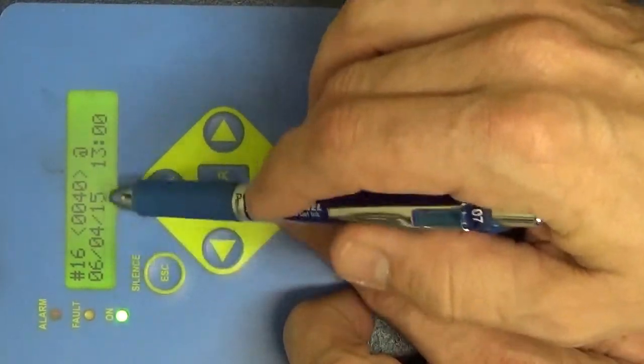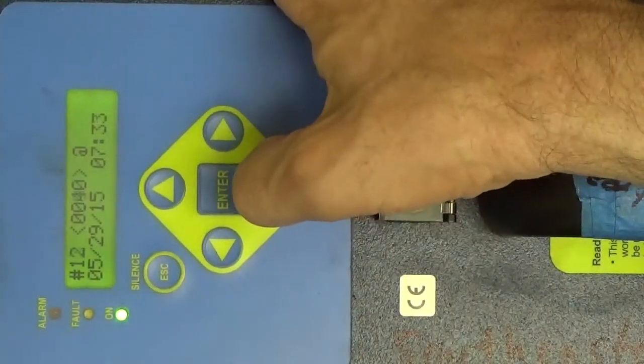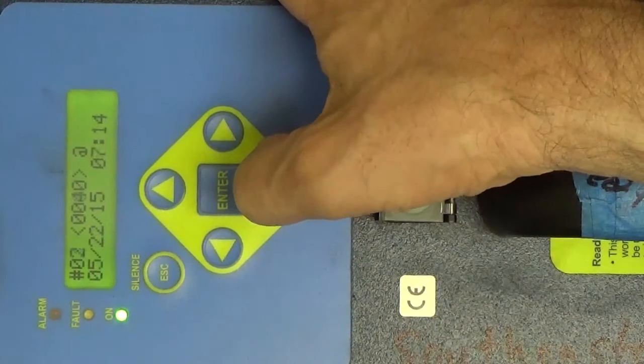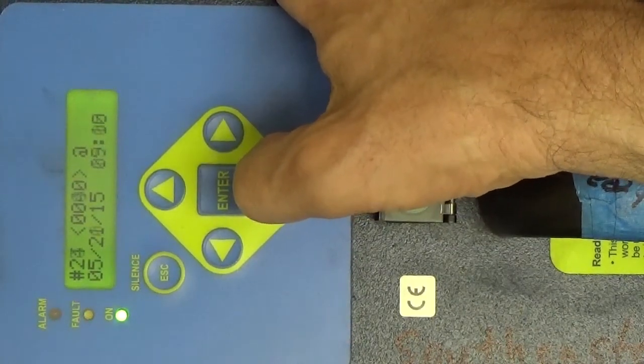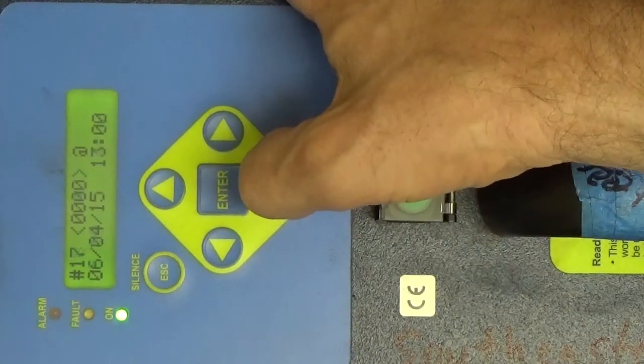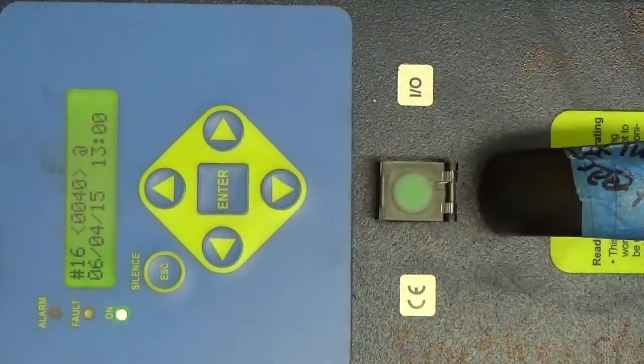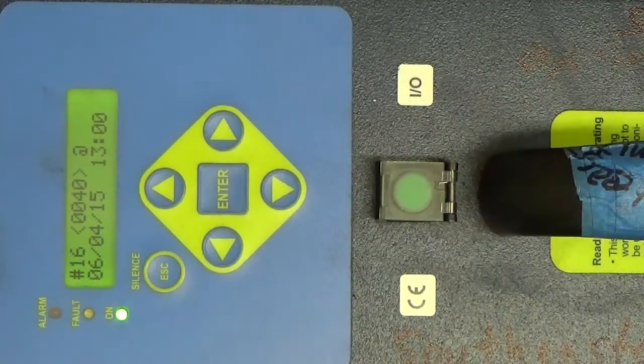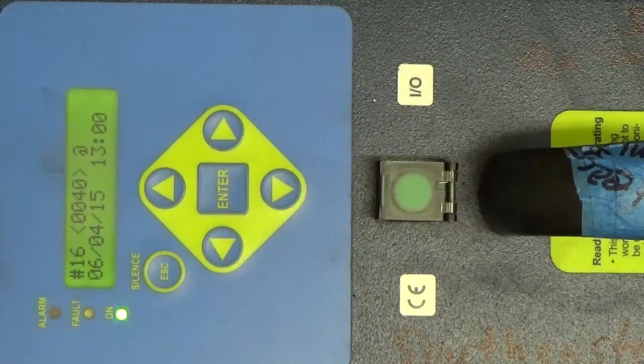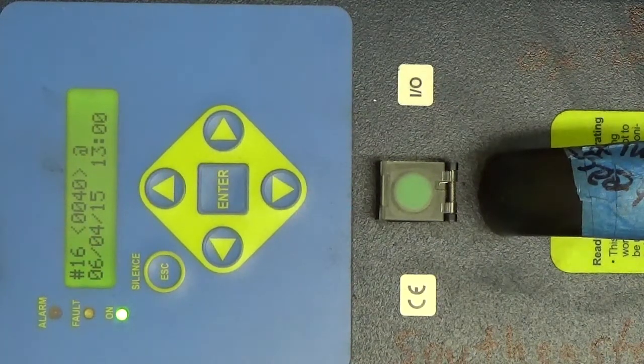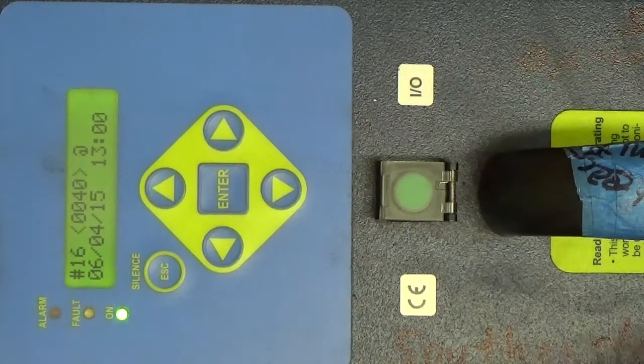As you move through them you'll see a fault code followed by the date the fault was recorded, and what I want to do is just take a quick breeze through here and see all the different faults that the instrument has been registering. This particular one has teetered between fault code 40 and no fault at all, and if you look at your documentation, fault code 40 is what's called a bag fill flow fault. So it's simply the internal fresh air bag from time to time doesn't fill as quickly as it should. That can point to a bag wearing out, could point to a lot of things. Not a critical fault, just something to keep aware of when we're doing the test.